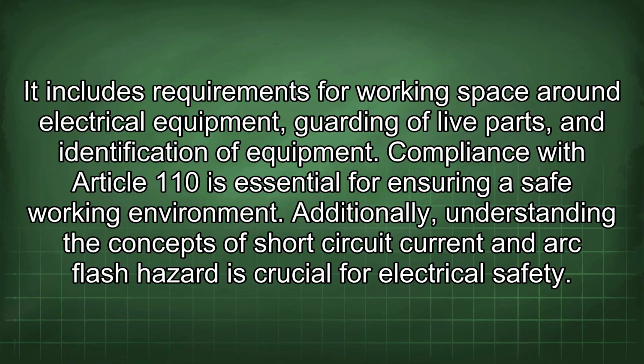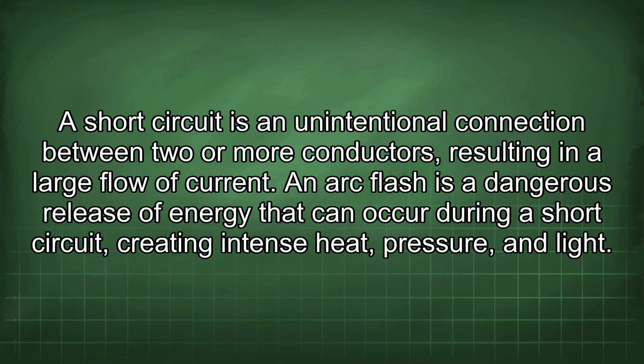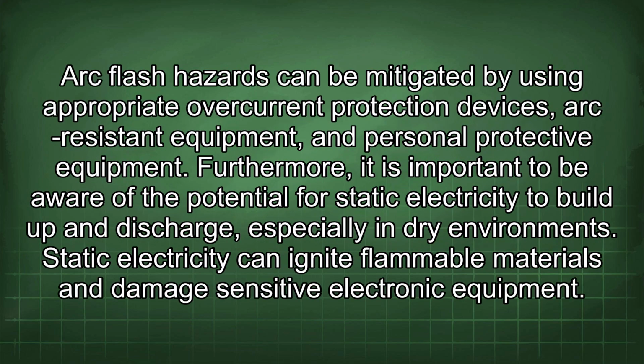Additionally, understanding the concepts of short-circuit current and arc flash hazard is crucial for electrical safety. A short circuit is an unintentional connection between two or more conductors, resulting in a large flow of current. An arc flash is a dangerous release of energy that can occur during a short circuit, creating intense heat, pressure, and light. Arc flash hazards can be mitigated by using appropriate overcurrent protection devices, arc-resistant equipment, and personal protective equipment.